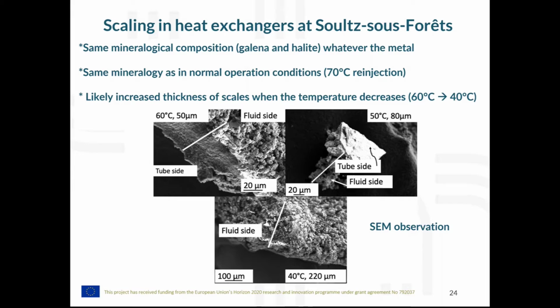We tested the influence of temperature on the thickness of the scales when the temperature decreases from 60 to 40 degrees. At 60 degrees, upper left corner, the thickness of the scale on a given metal is 50 micrometers. You see on the top of this figure the fluid side, which is rough, and the tube side, which is smooth. When the temperature decreases to 50 degrees centigrade, the thickness tends to increase up to 80 micrometers. On the lower figure, we see the thickness has increased up to 220 micrometers at 40 degrees centigrade.